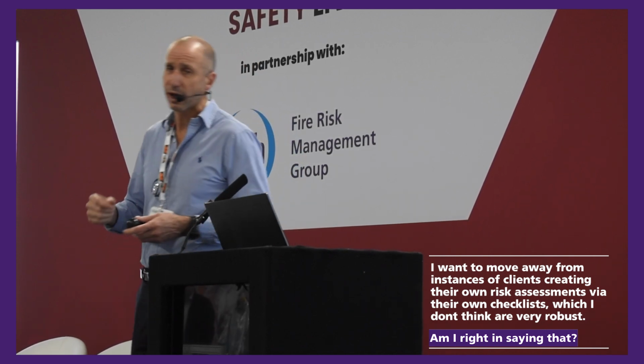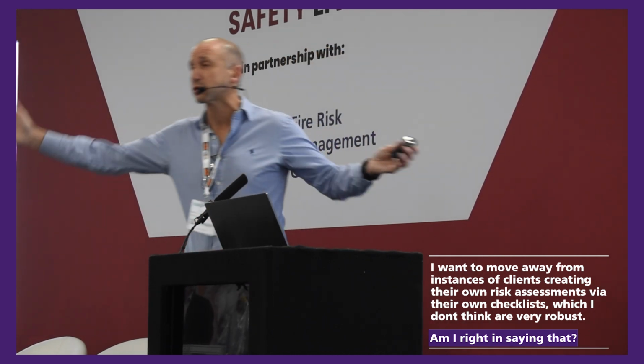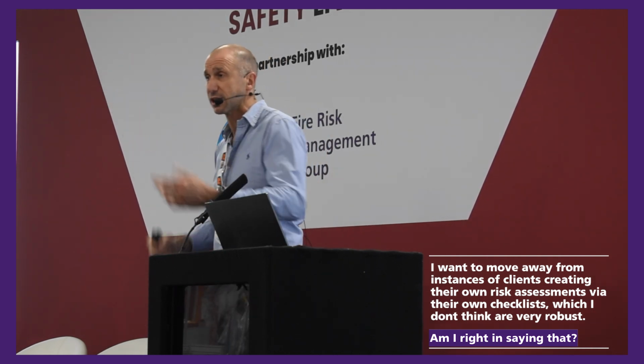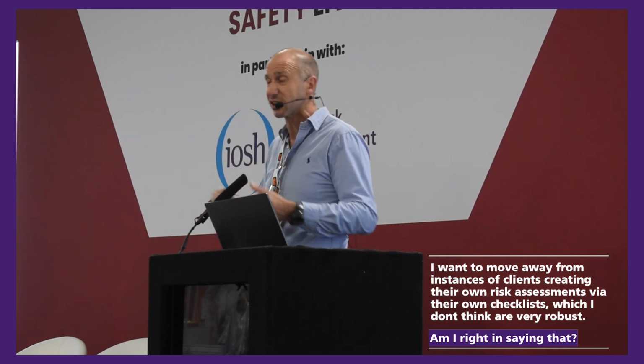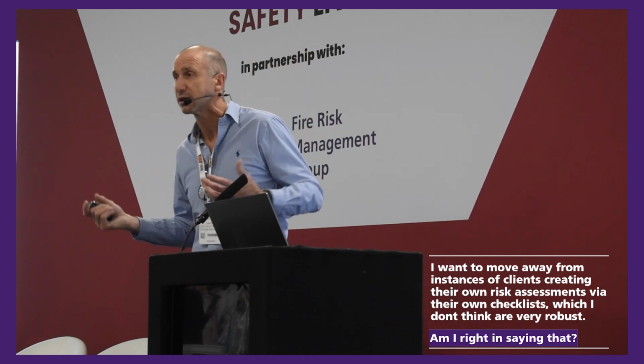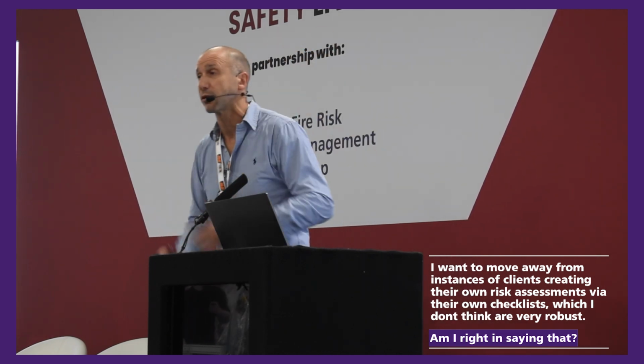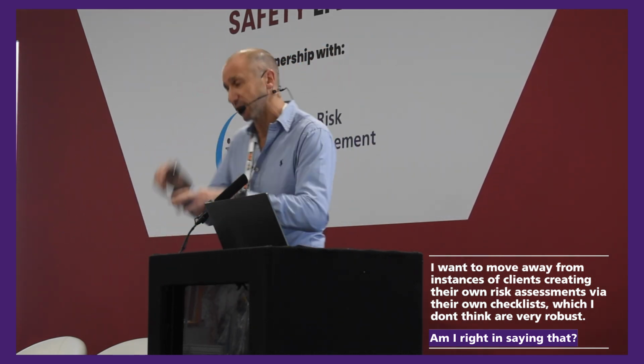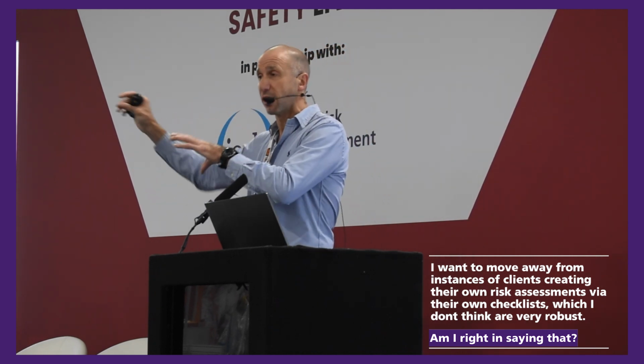And there could be an aspect where, for example, the travel distance is over 18 metres, single travel, it could be 25 metres. Well, that might not be a problem if you can justify other aspects. If you're just ticking the box, yes, it's all suitable, sufficient, that really isn't justifying it. It might be, is there a fire alarm system and does it work? Yes. Well, instead of perhaps being an L4 system where it's just on the common parts, it could be an L1 system, so it's everywhere. Well, actually, a fire will be discovered quite early, so you might get away with an extended travel distance. So if you could put that commentary, then ultimately that will help you justify your factors.